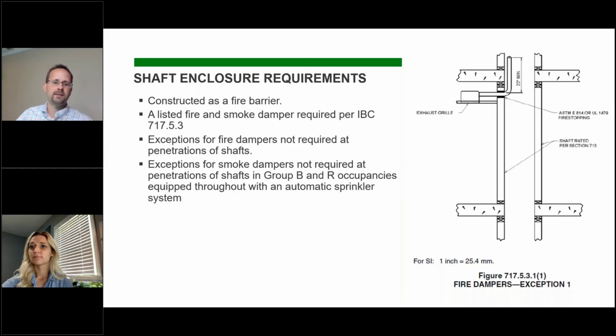So if you have a system that, for instance, has stacked restrooms or stacked dryer vents, there are a few times where you would not want to put a fire smoke damper in each penetration into a shaft. So there are allowances in this section of code to talk about what you can do to avoid fire smoke dampers when you go into a shaft. And what that includes is a couple of different things. First of all, the opening would have to go into the shaft and have a 22-inch steel subduct.